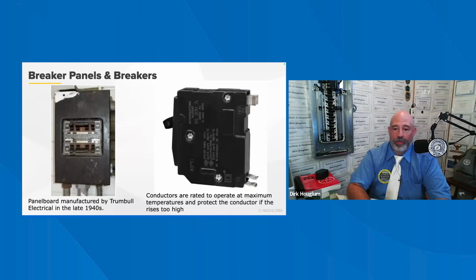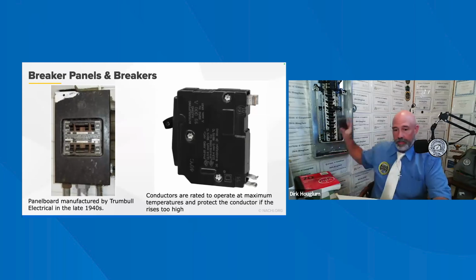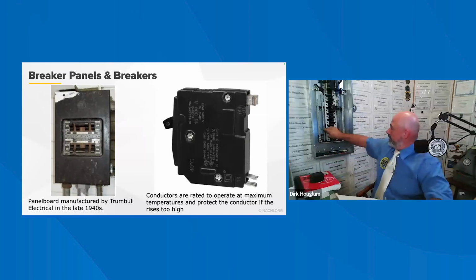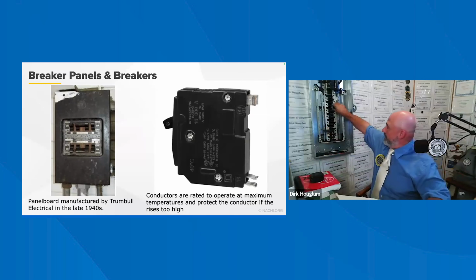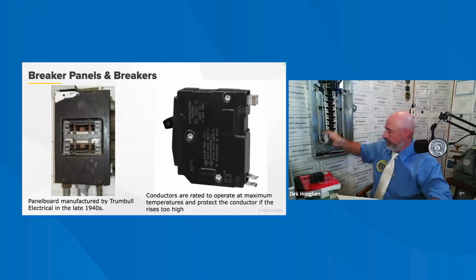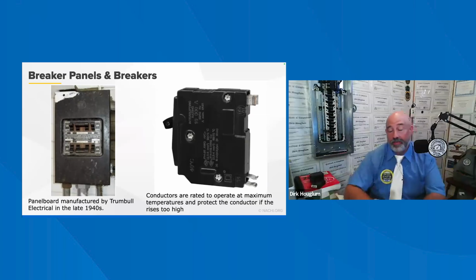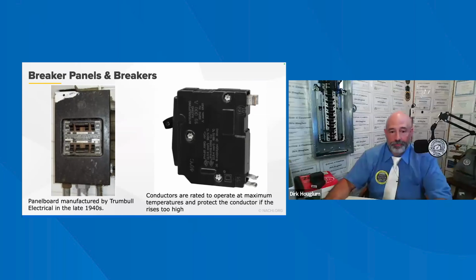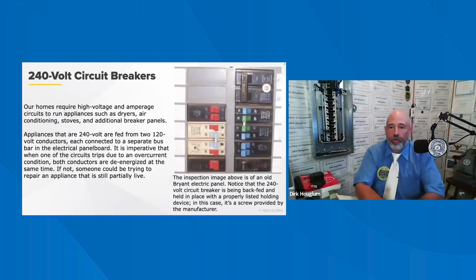You've got the 240 volt double breakers. That would be this guy right here. The single 120 volt is this one right here. Okay, now I won't be able to get that back in. Then there are the GFCI breakers that were introduced in the 1970s, and the AFCI breakers that were introduced in 1997 and became code in 2002. Okay, the 240 volt breaker has 2 handles that move together.